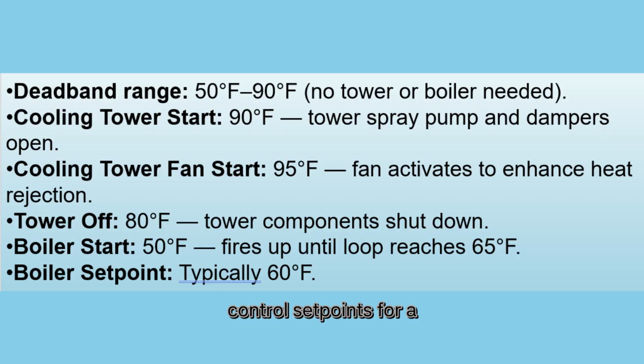Here are the standard control set points for a WSHP loop. The system operates within a deadband range of 50 degrees Fahrenheit to 90 degrees Fahrenheit. When the loop stays within this range, neither the cooling tower nor the boiler needs to run. The system simply balances energy between zones. When the loop temperature reaches 90 degrees Fahrenheit, the cooling tower spray pump and dampers open to begin rejecting heat. If the temperature continues to climb to 95 degrees Fahrenheit, the tower fan starts to enhance heat rejection and bring the loop temperature down.